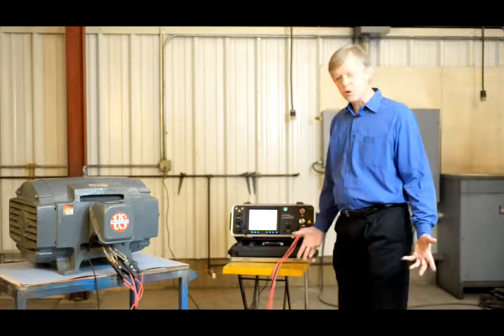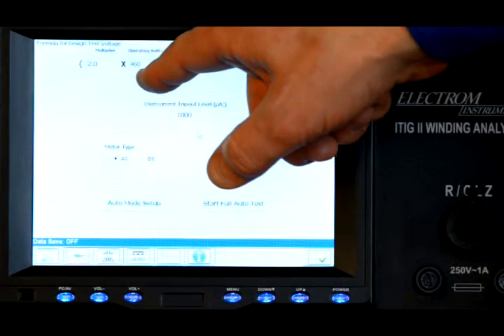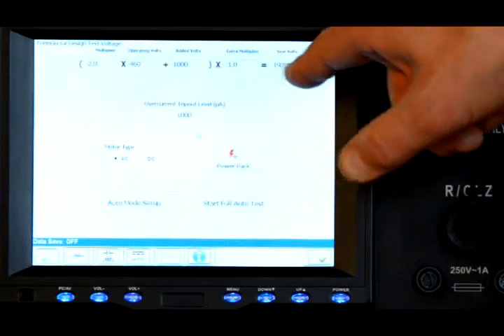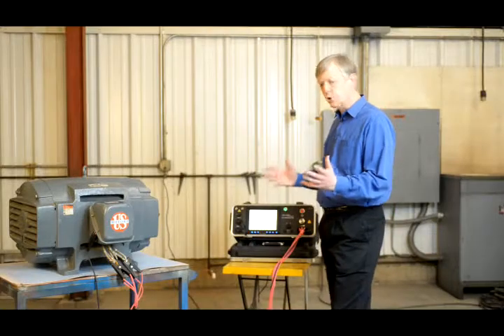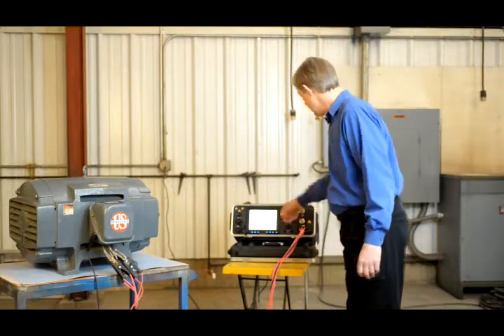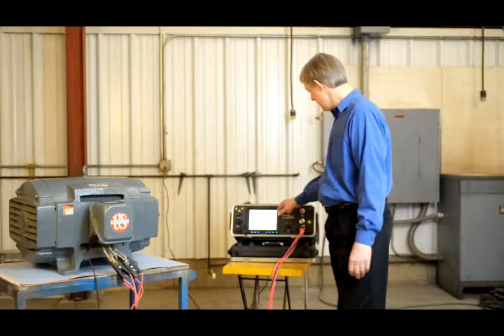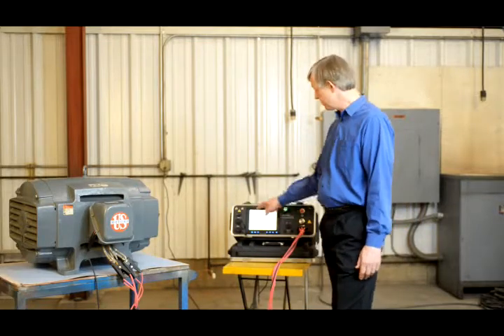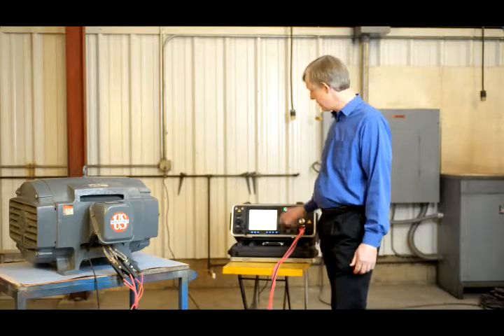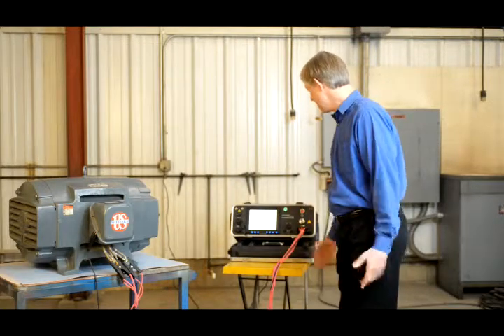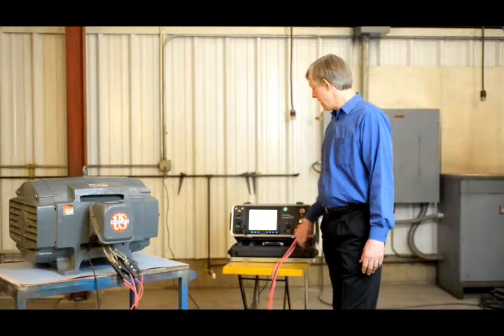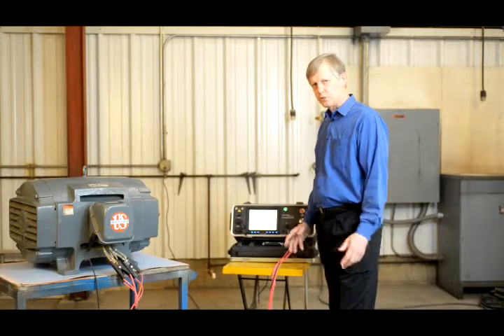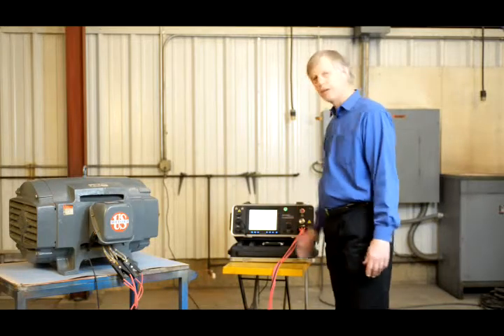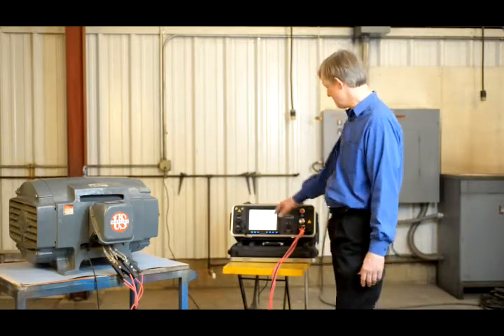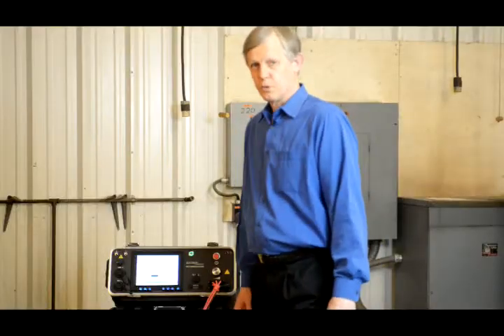That brings us to the setup screen, which has a formula on the top which tells you what voltage we will be testing to in the high voltage parts of the test. Today we're just doing a 460 volt motor here, so we're testing to 2 times operating voltage plus 1000, which gives us the number indicated here, 1920. You can also make adjustments to the overcurrent trip out used in megohm and high pot. We are going to leave those at 1000, which is what we have on the screen. So the first test we will do is the winding resistance measurement.